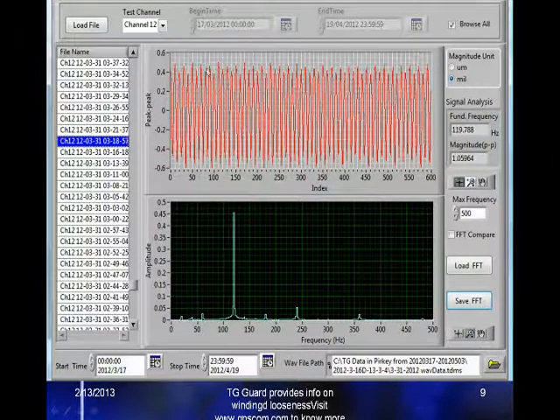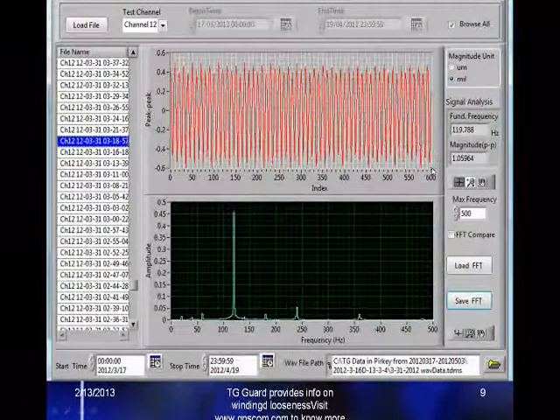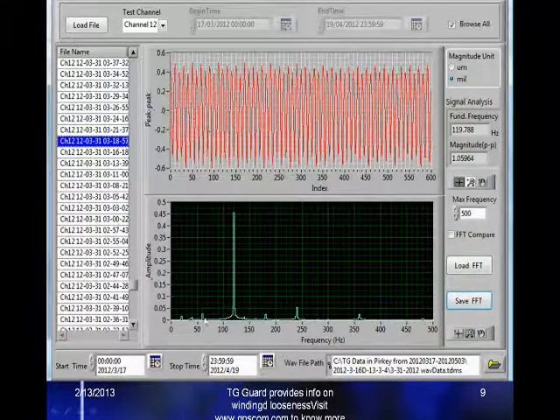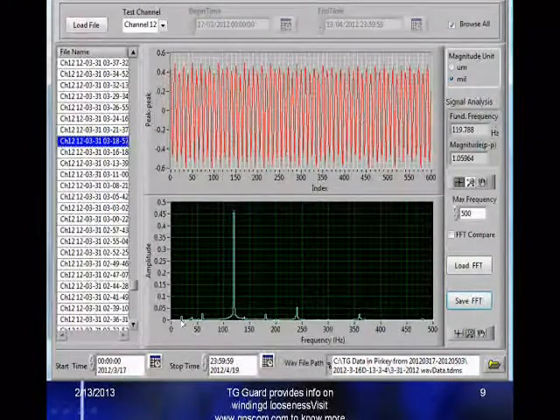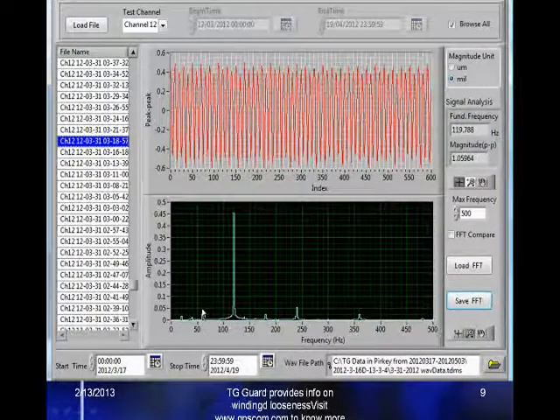Now, take a sample of the time domain waveform, and there you will see a frequency fast Fourier transform, validating that the vibration signal is mainly 2 times line frequency, which is very clearly shown here. What is mysterious is that we have different frequencies distributed both on the low end and the high end. They are not exactly harmonics either. Let's say the primary frequency is shown to be 120. Here there is a small harmonic at 240. But what about these little peaks? They are 30. Well, what about the 1x?